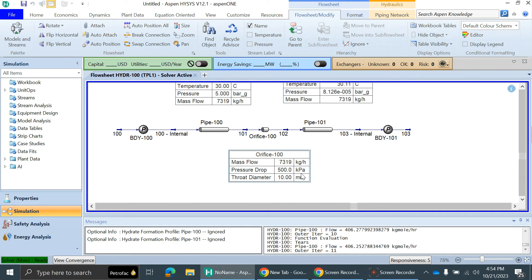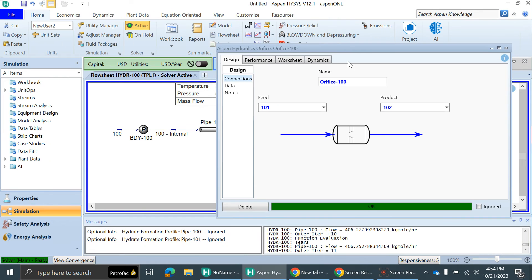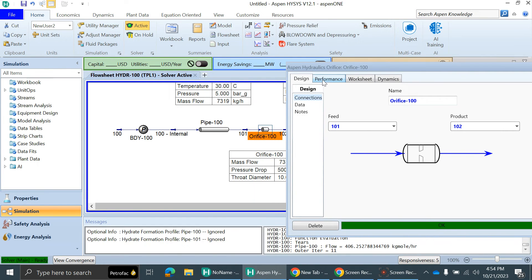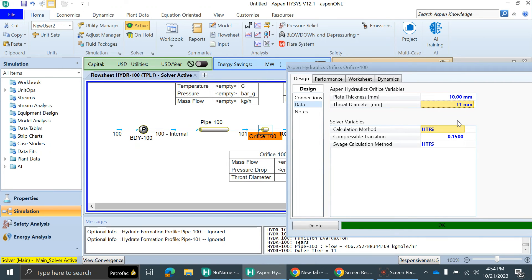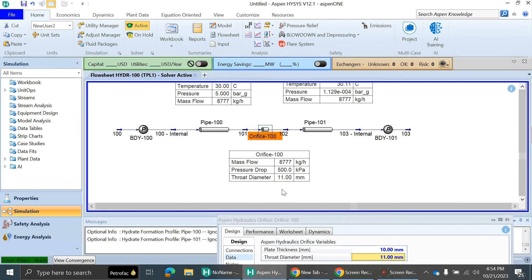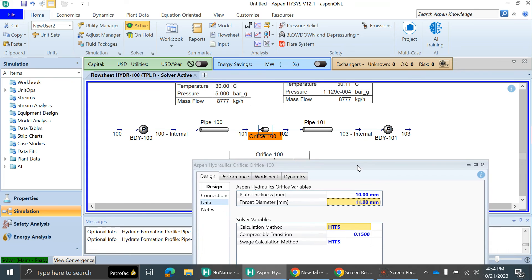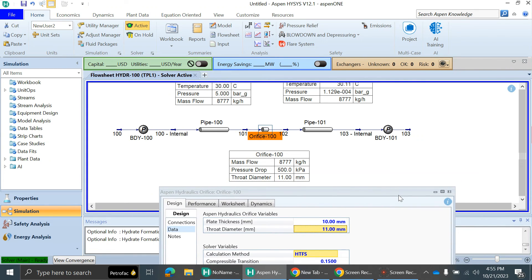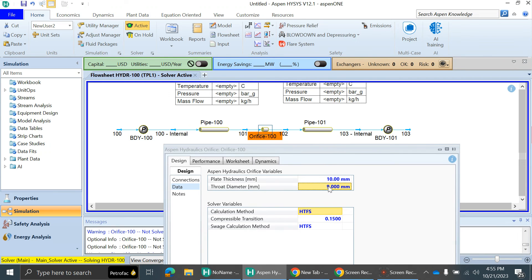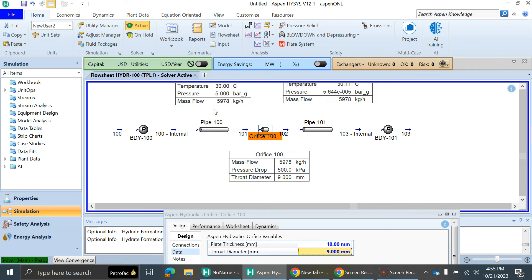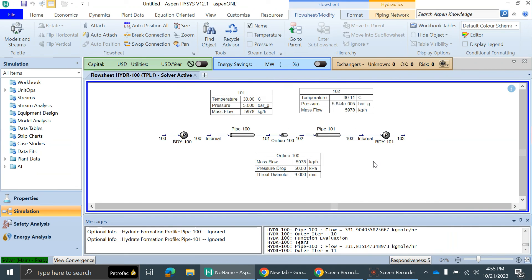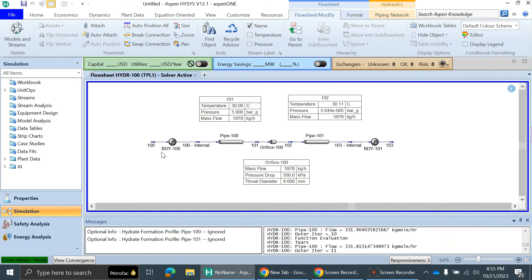Let's see what happens if we increase the throat diameter. Suppose I'll make it 11 mm. You can see when I make it 11, the flow rate increases because at 5 bar gauge pressure drop, the flow will increase because the area is increased. Suppose I make it 9 mm. You can see the flow rate decreased. In this way, you can size the orifice in HYSYS.